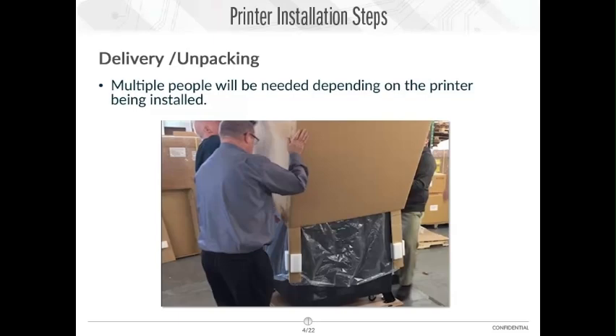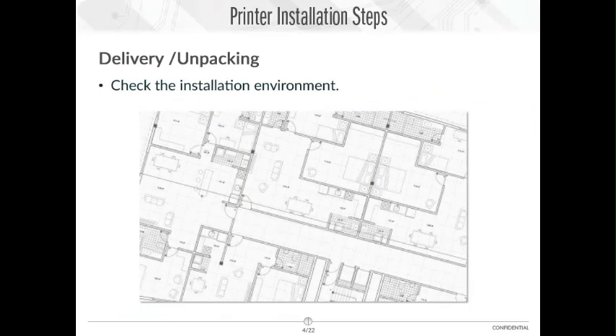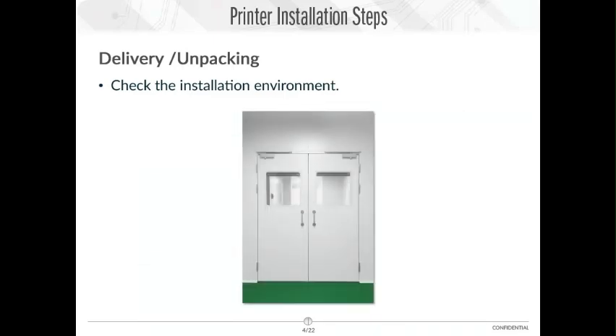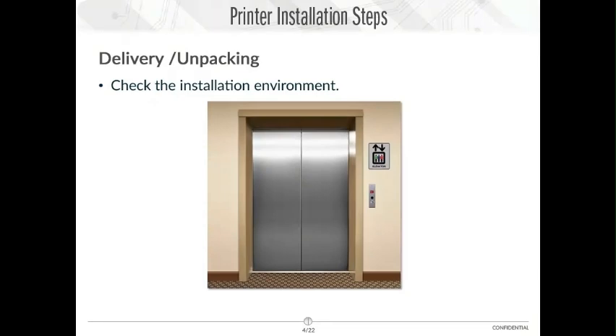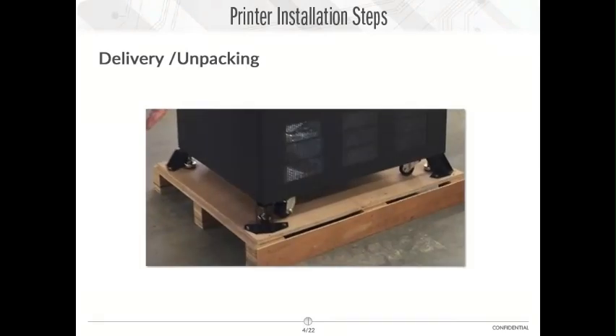Check the installation environment before unpacking the printer. Make sure the doorways that the printer will need to move through are wide enough, and that the floor surface where the printer is to be placed is level. If the printer needs to be located on a different floor of a building, the elevator will need to accommodate the equipment and personnel moving the equipment. Some of the printers are equipped with casters. This will aid in moving the printer to its location.